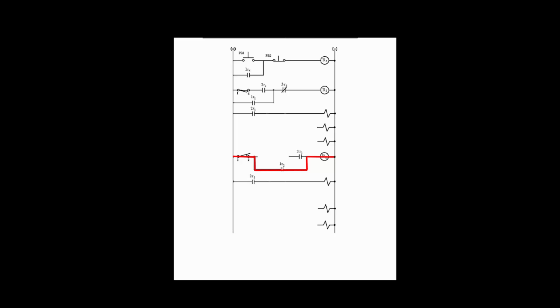To repeat the cycle, R1 is to turn on again by this limit switch, which is controlled by the last action of a given sequence. This again causes R2 and R1 to turn on at the same time. When R1 is again turned on, R2 is turned off by this special normally closed but held open limit switch, which is controlled by the last action of a given sequence, slightly different from the way R1 is turned off.